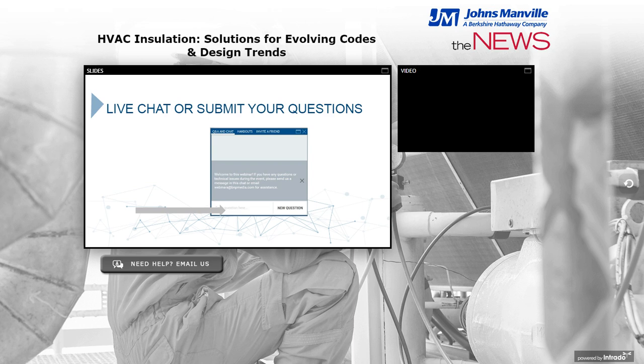Good question. Crawl spaces are typically seen in residential applications. A lot depends on what area of the country you're in and what's being requested of the application. I've seen flex duct run through crawl spaces, sheet metal duct wrap, sheet metal duct lined, and you could even use duct board as you run through the crawl space. It's inside, not getting wet, not exposed to direct or outside moisture. Definitely something with a foil vapor barrier of some sort. But you can really use what you'd like in that application because you're still undercover—it's not wet, not necessarily exposed to the elements—so you can design that system with what you prefer.